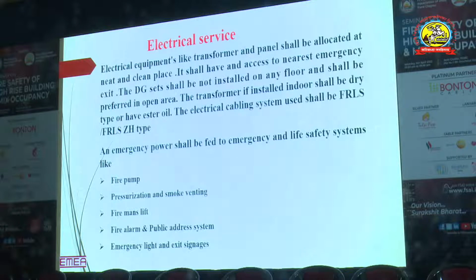The electrical services, whenever we are doing any plan with the architect, are always a priority. That said, priority is not given so seriously to the electrical substation or electrical layout, size-wise and from an access point of view. This point has to be considered very important from the design stage itself. Electrical equipment like the transformer and panel shall be allocated at neat and clean places. An oil-type transformer requires at least 6 by 6 meter open space. It shall have access to the nearest emergency exit.